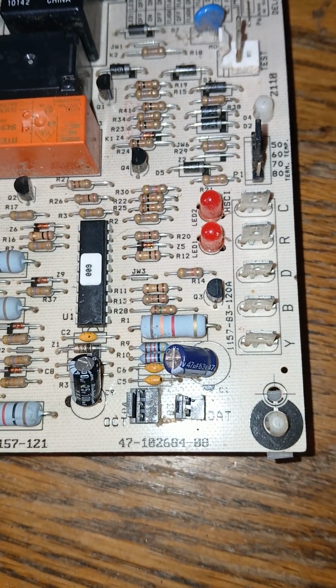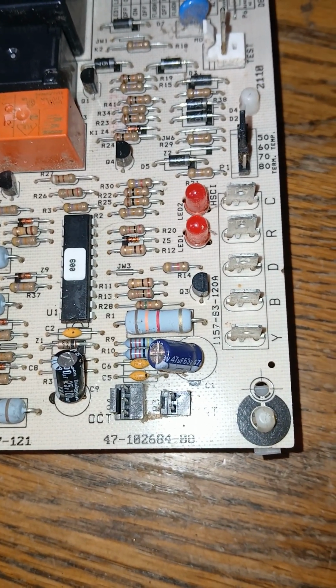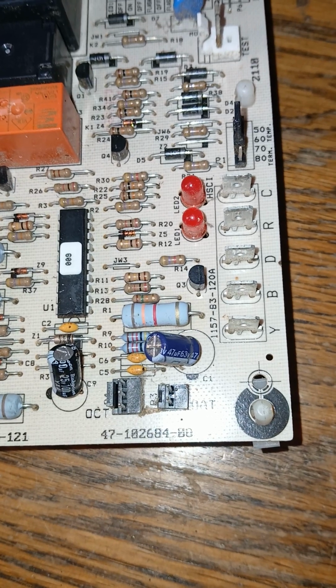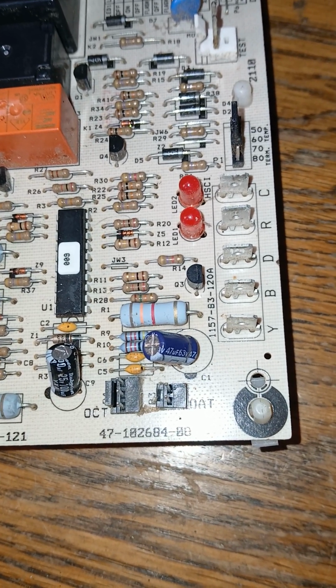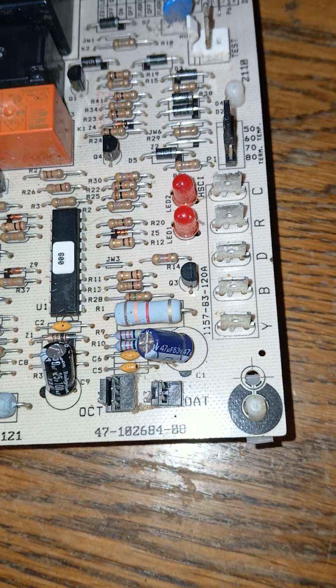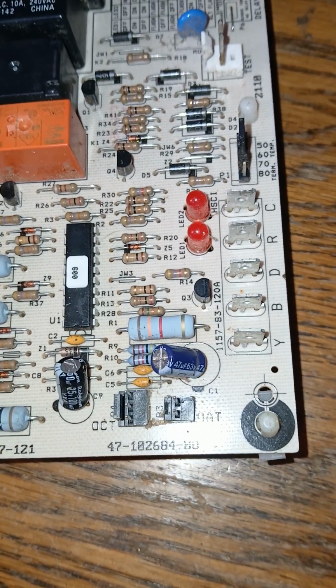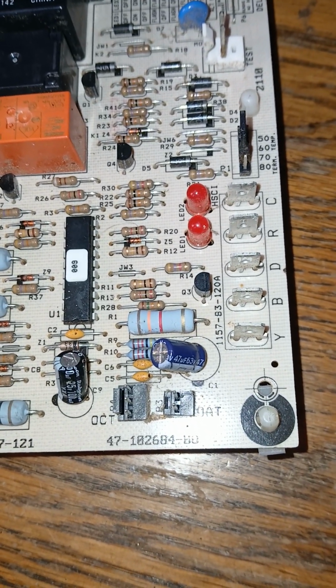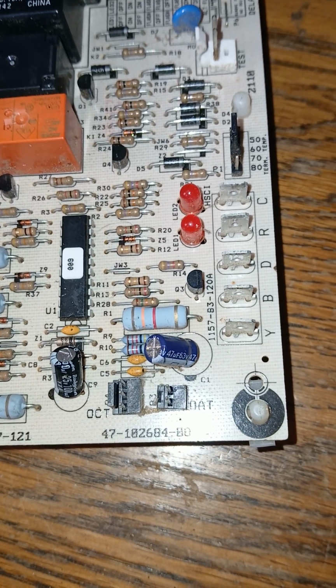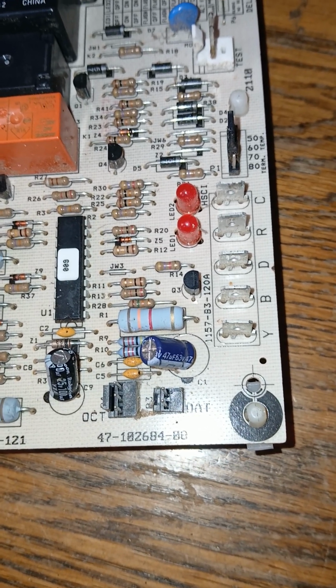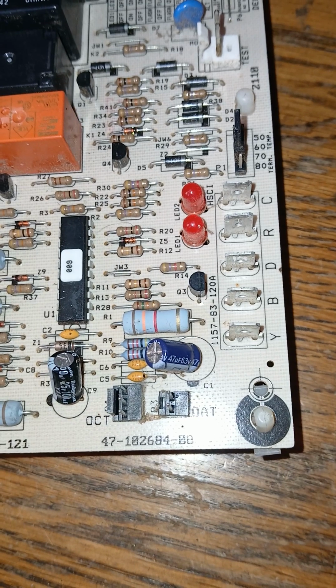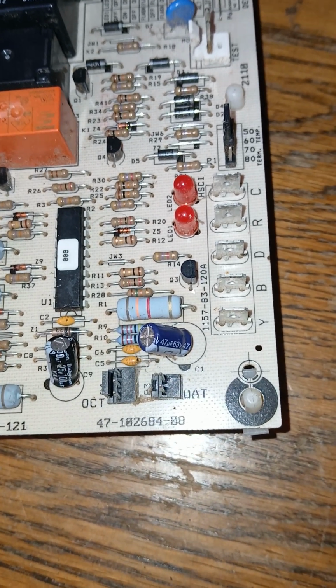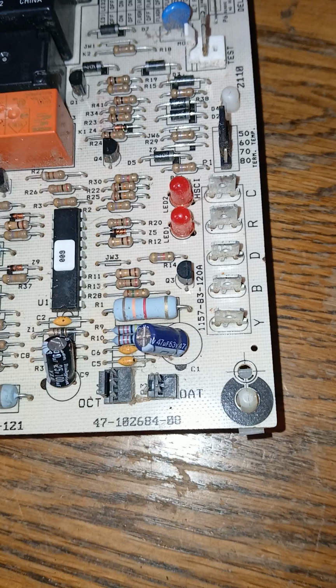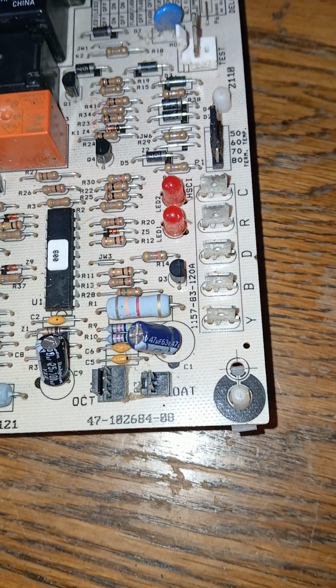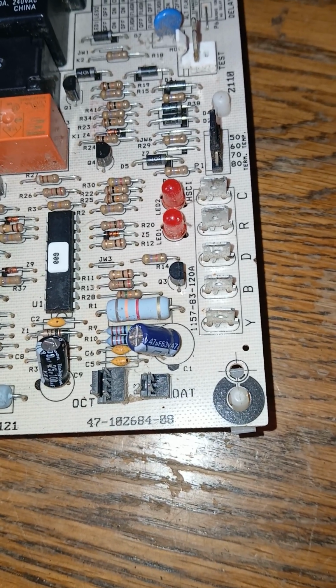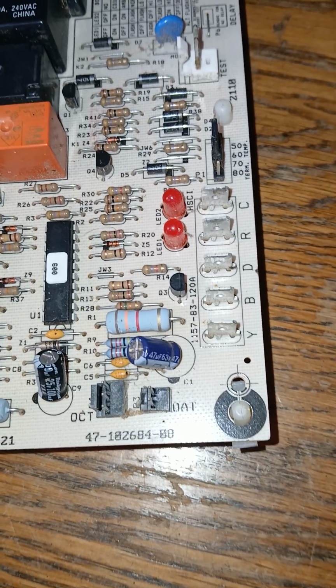Defrost control board for a heat pump. There are a sundry of different manufacturers of defrost control boards, and many operate in a similar fashion. They may be configured slightly differently, but the functionality is pretty much the same. They're there to defrost, to get the ice or frost off of the coils. It may be time delayed.